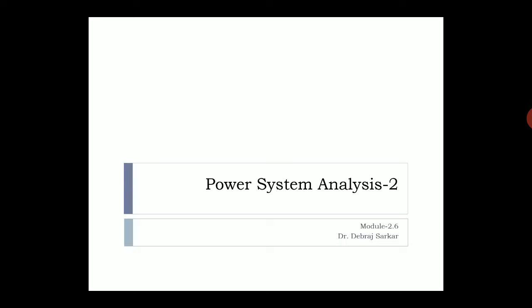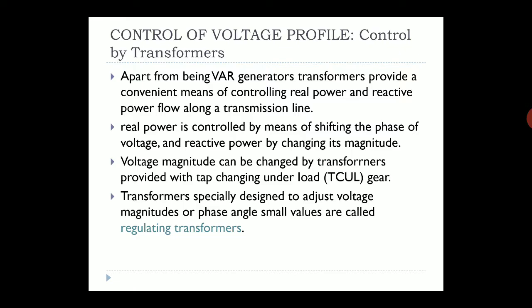It is not only the voltage but also the voltage angle. Generators were controlling the voltage angle by controlling the reactive power flow and the real power flow, which changes the voltage magnitude as well as the voltage angle. Transformers can also be used to control voltage. There are two different types: one controls the voltage magnitude and the other controls the voltage angle.